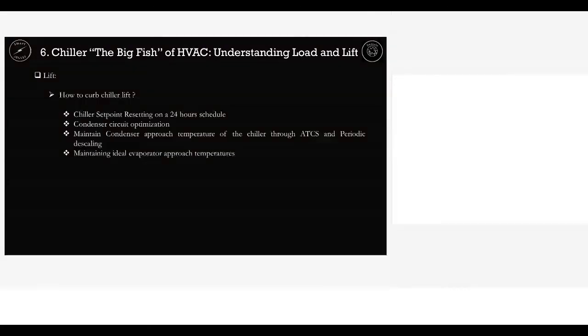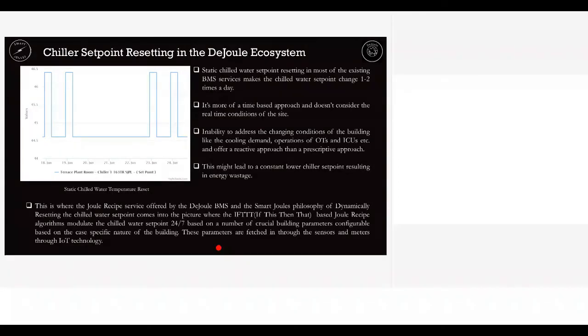So how to curb it? Chiller set point resetting, that is, changing the chiller set point at different times of the day. Condenser circuit optimization, maintaining condenser approach temperatures, I will go into later. If you do all these things, you can improve efficiency and save energy from the equipment. So what is chiller set point resetting in an ordinary building and how do we do it differently? The temperature of the cold water leaving the chiller to the building is what we call the set point.